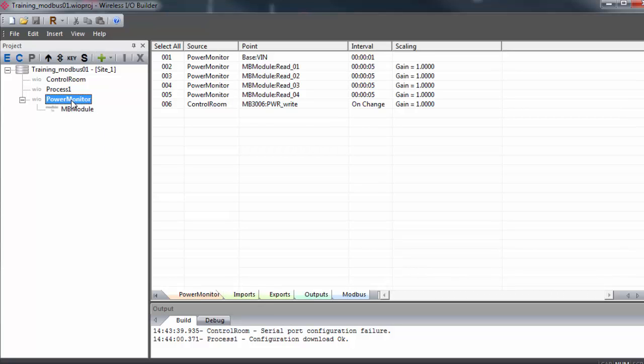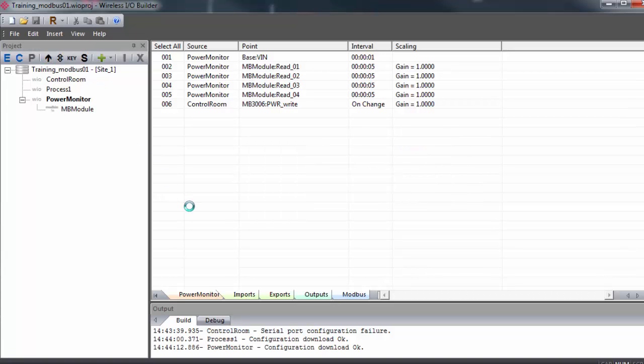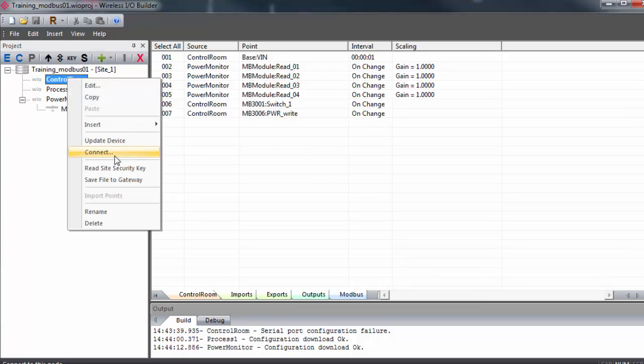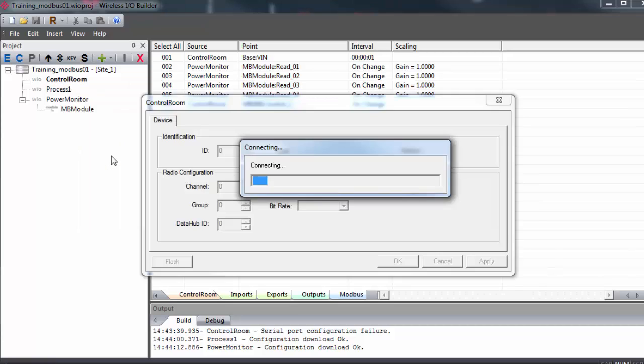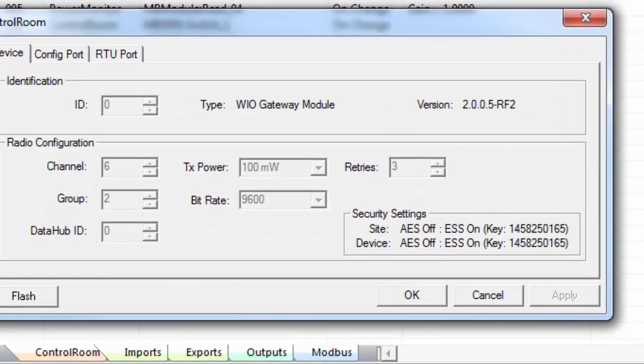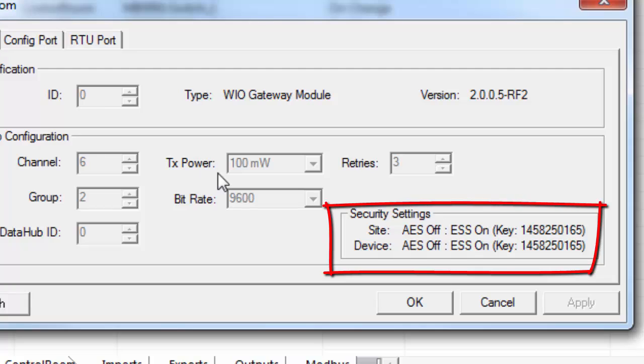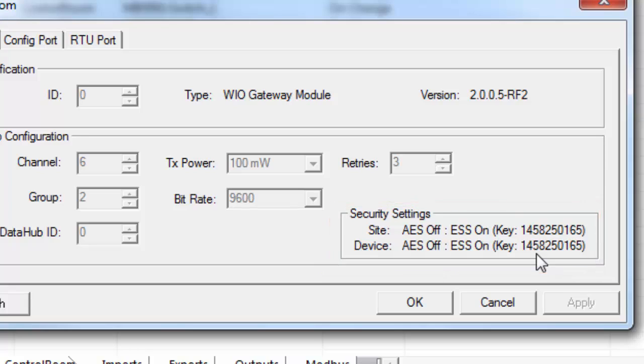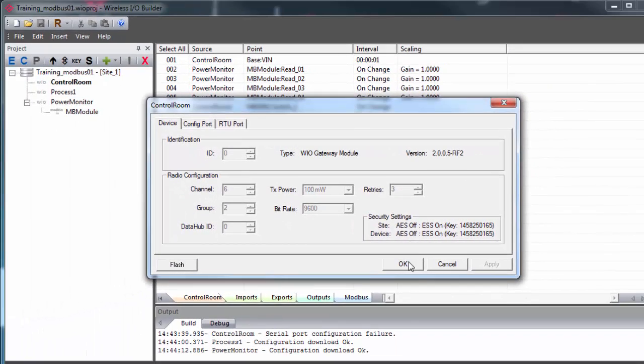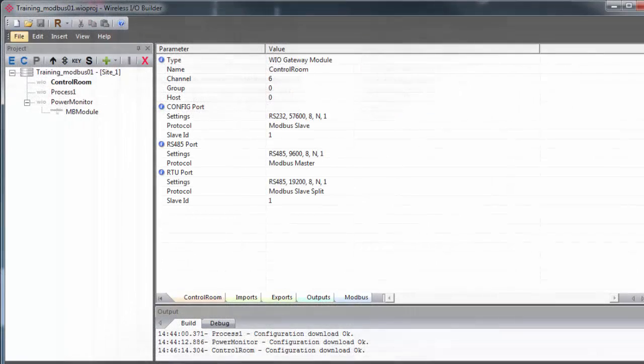One important thing to note is the Site Security Key function. The multi-point wireless I.O. gateways are designed to only communicate with other multi-point wireless I.O. gateways that have the same security key in their configuration files. When you create a new project in ProSoft Wireless I.O. Builder, a new Site Security Key is automatically generated, and every gateway that's updated with this project file will be assigned that security key.